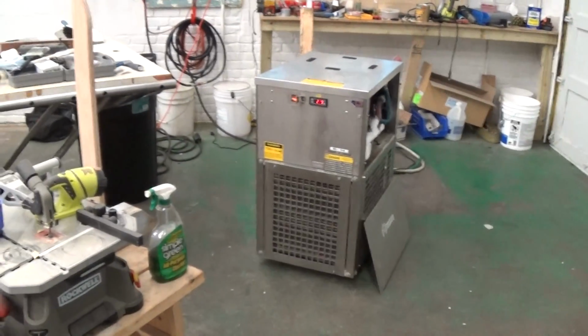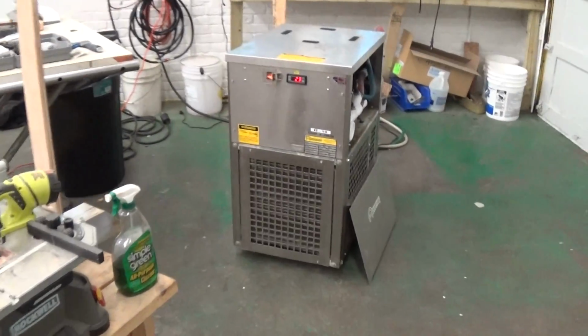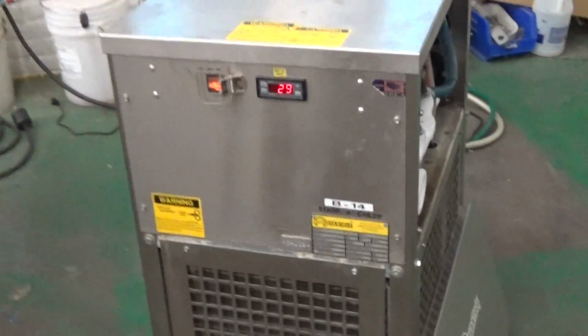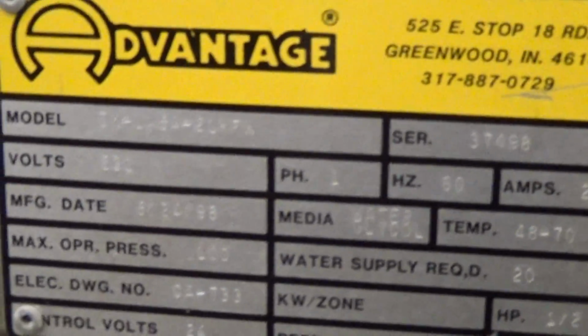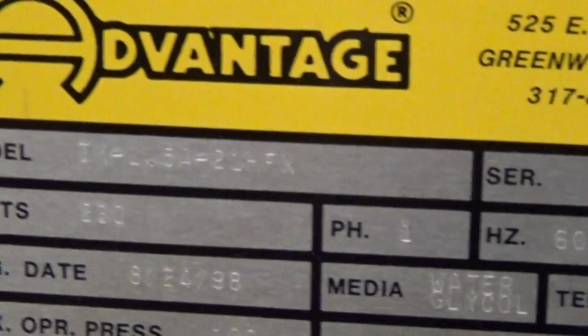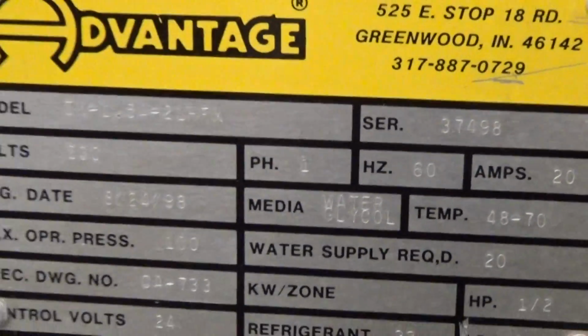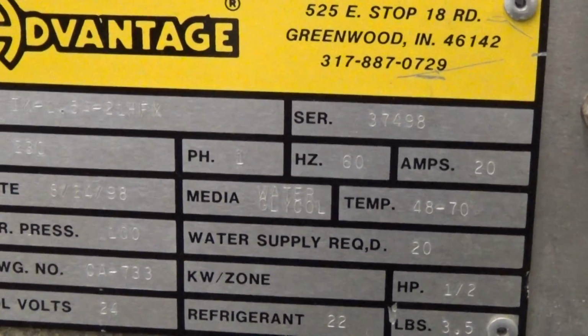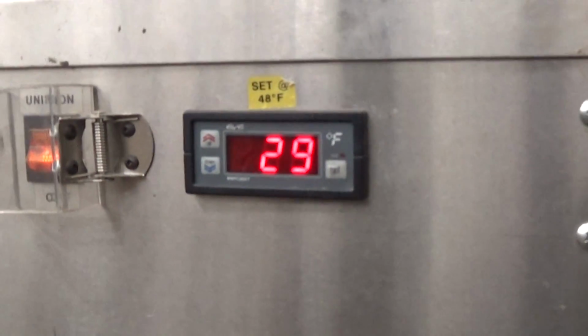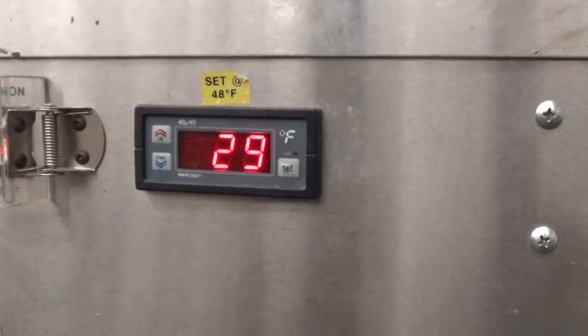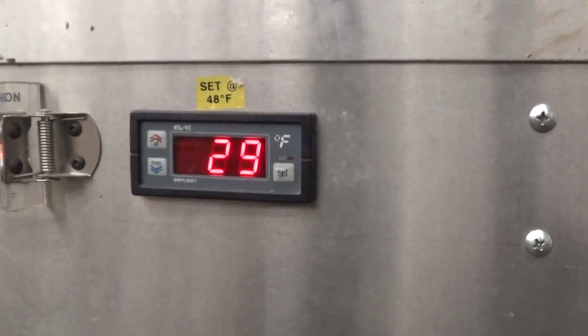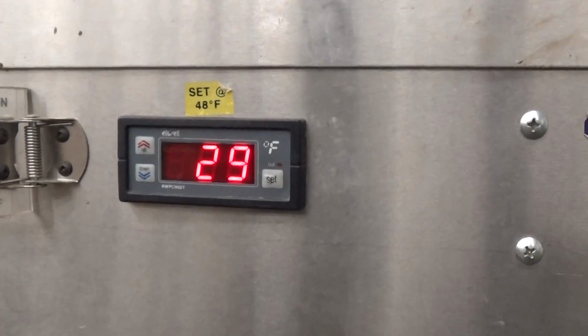It's Monday, November 9th, and we're going to take a video today for a 1.5 ton, 1.5 horsepower air-cooled chiller for a customer. In fact, the pump is running right now. You hear some noise in the back of the shop. Sorry about that. But the pump is running right now. In fact, we have a set point set of 30 degrees. And we've actually been running this unit for 2.5 days since Friday, and it's Monday morning right now. We never turned it off.